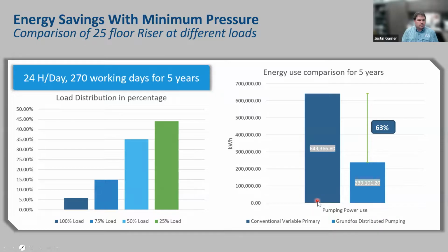operation. So if we look at this in that same building, that 25-story building, and we look at it as a certain amount of working days for a chilled water system over a period of time, we start to see that energy use. In this case, we're looking at 63% less pump power. So that hydronic distribution pumping power energy that we're talking about would be 63% less in a distributed pump system, by putting that pump power out at the loads, as opposed to a large centralized pump plant down in the basement and then reducing the excess pressures with mechanical devices.